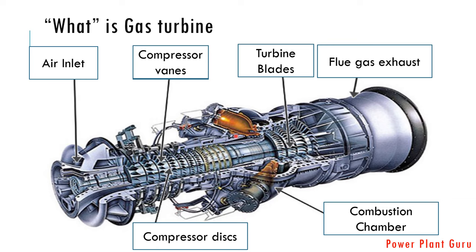There will be a spark plug, so a spark is generated and flames are created. These combustion chambers are arranged in a 360-degree annular type of arrangement and are connected to each other. Once a spark creates a flame and it is established in one chamber, it will pass through all the 10 or 14 combustion chambers — it may be 10, it may be 14, it may be 20 also, based on the capacity of the machine.